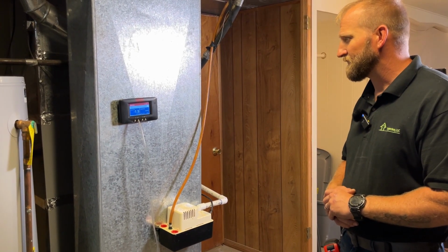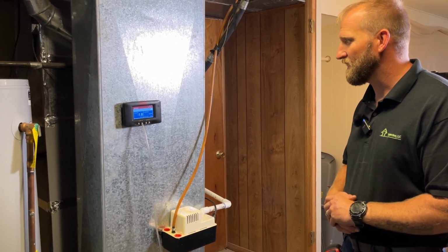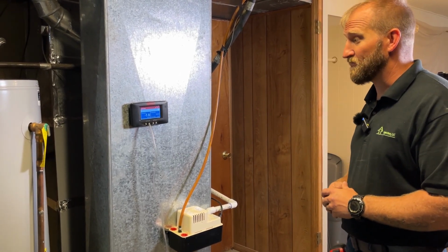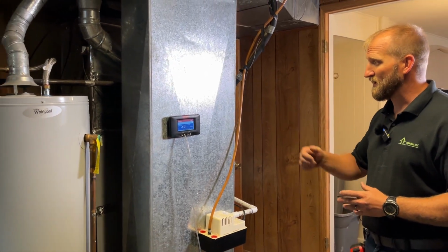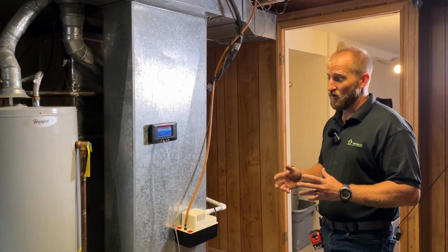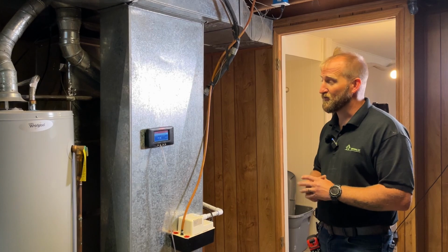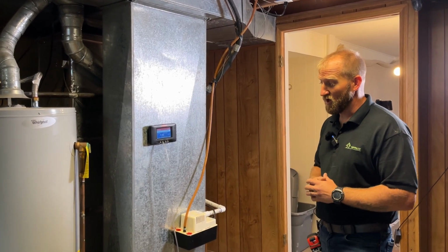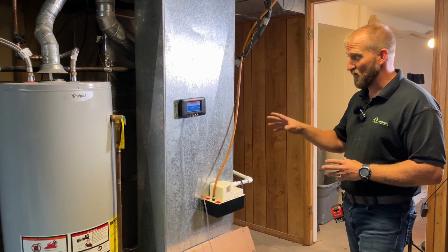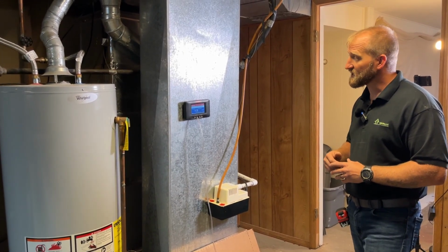And see if that changes anything. Still sitting around that 1.7 to 1.9 mark. So we can call that depressurization, around a 1.7, 1.8, just bounced up to 2 a little bit. So we're under the old BPI threshold on that. So once we've got that done, we're going to go ahead and write down our worst case depressurization.